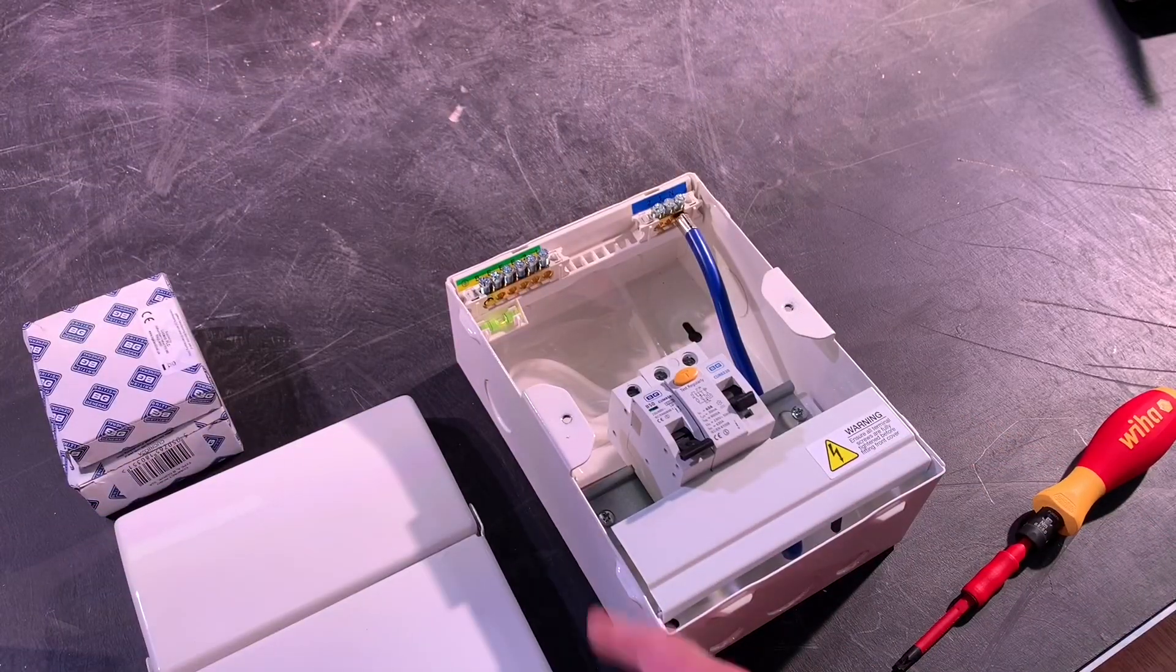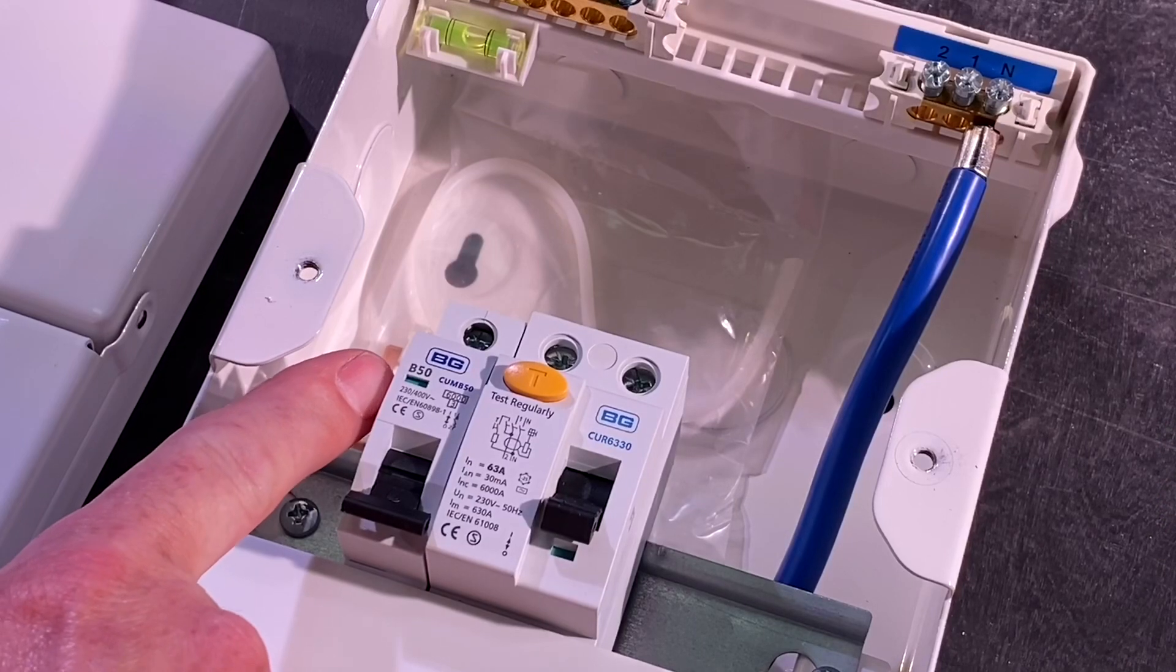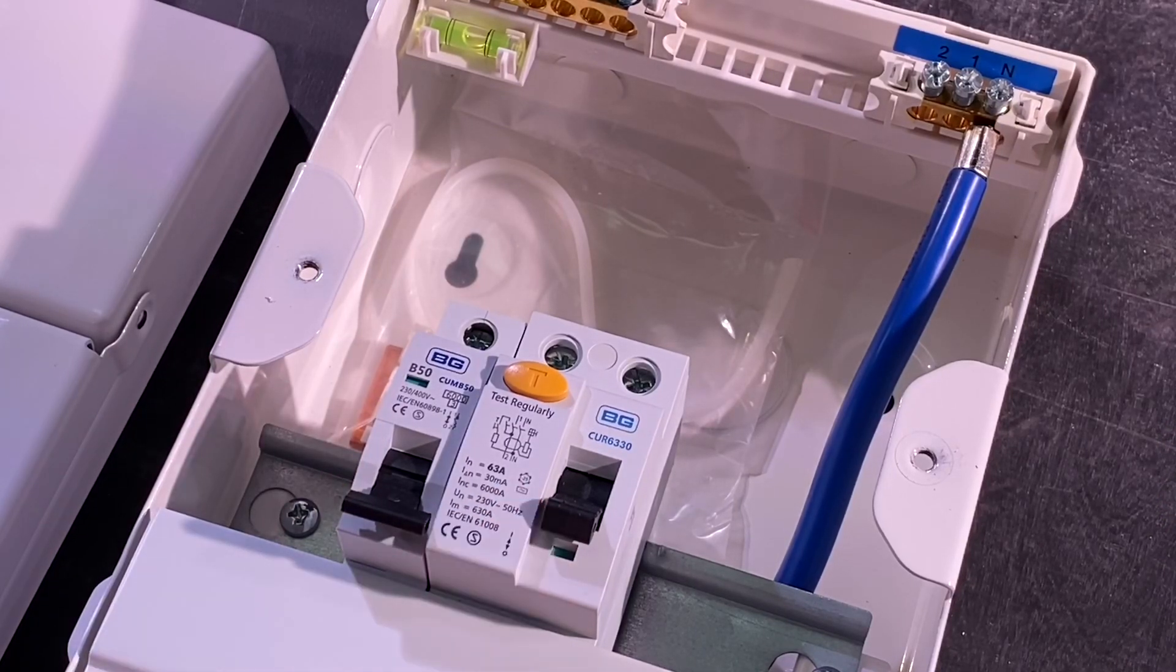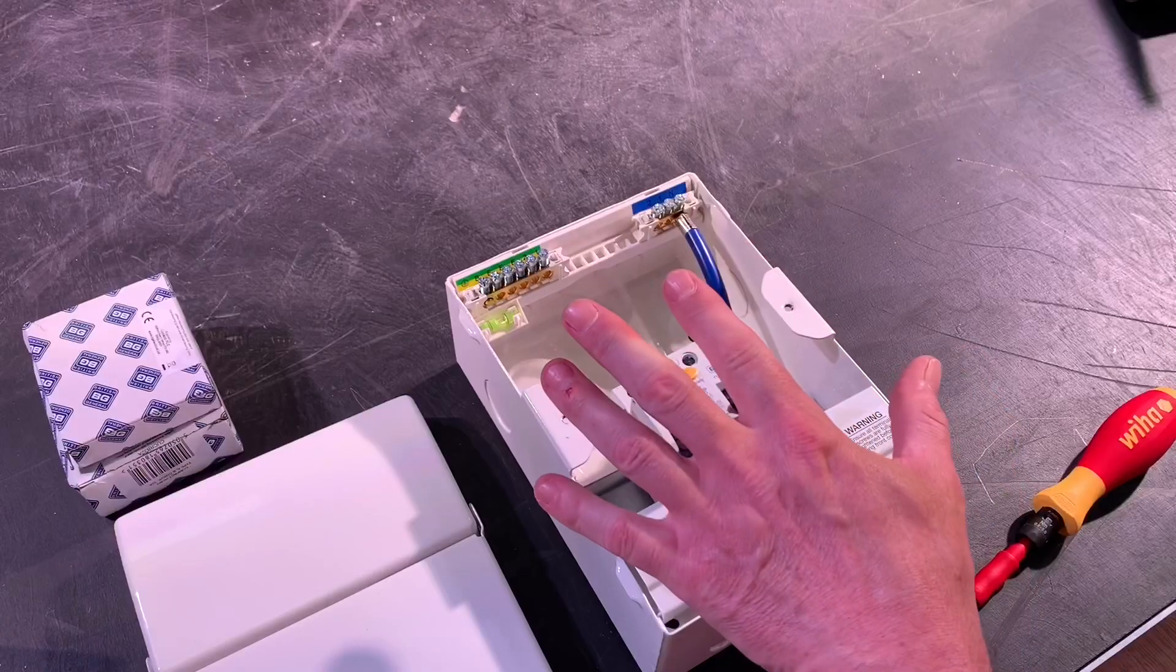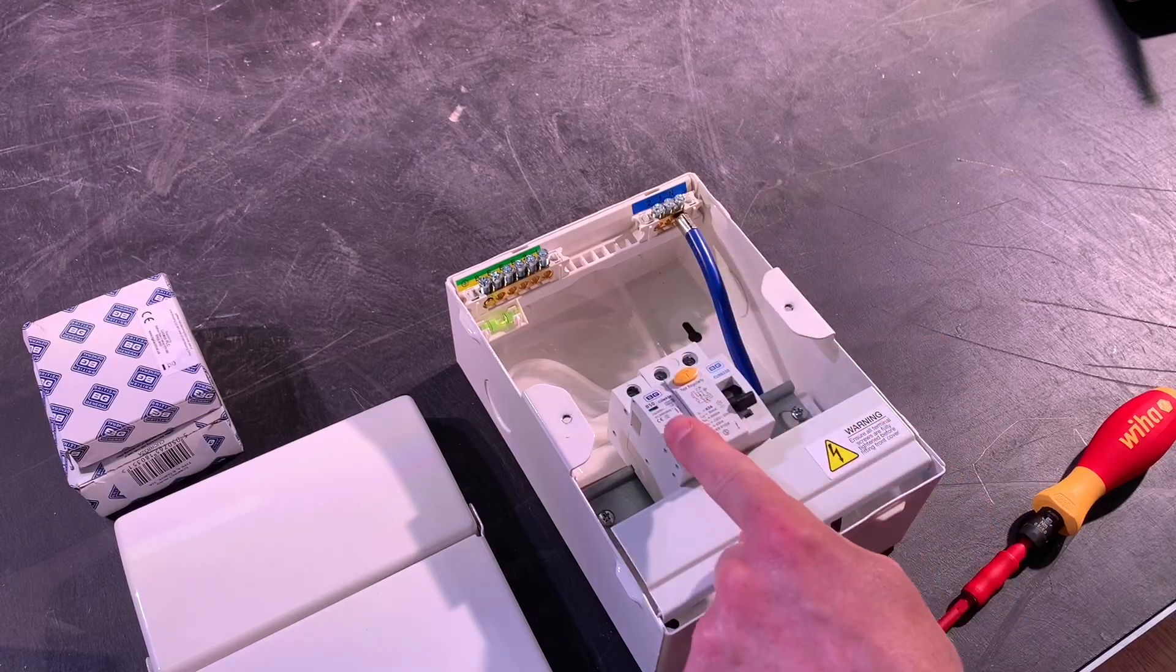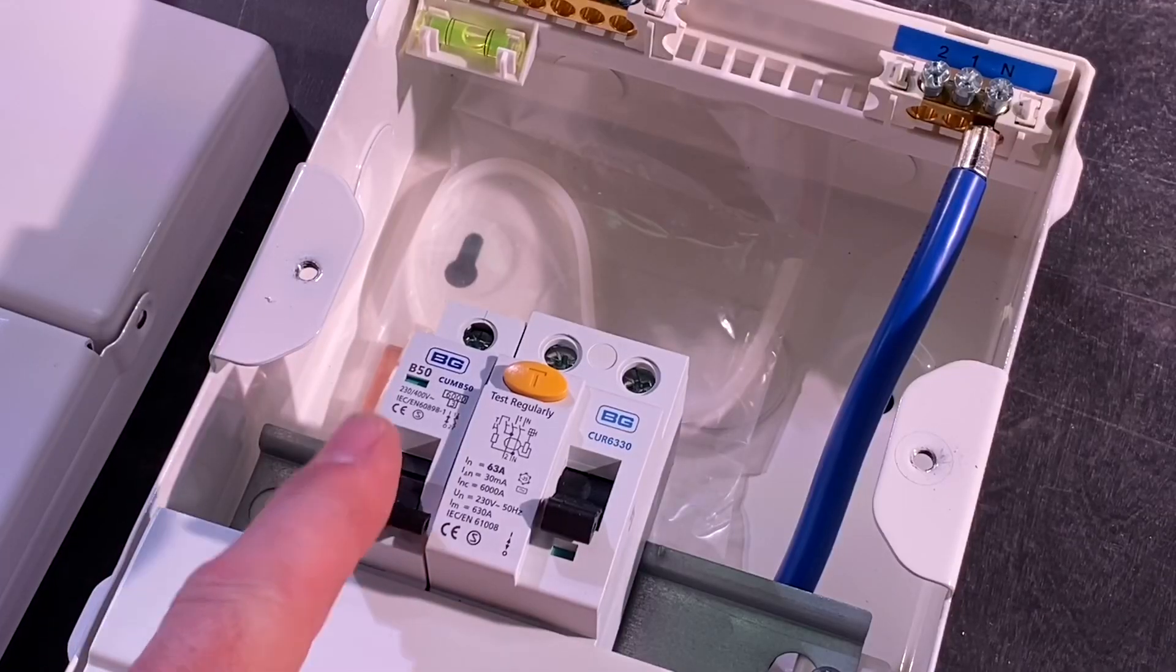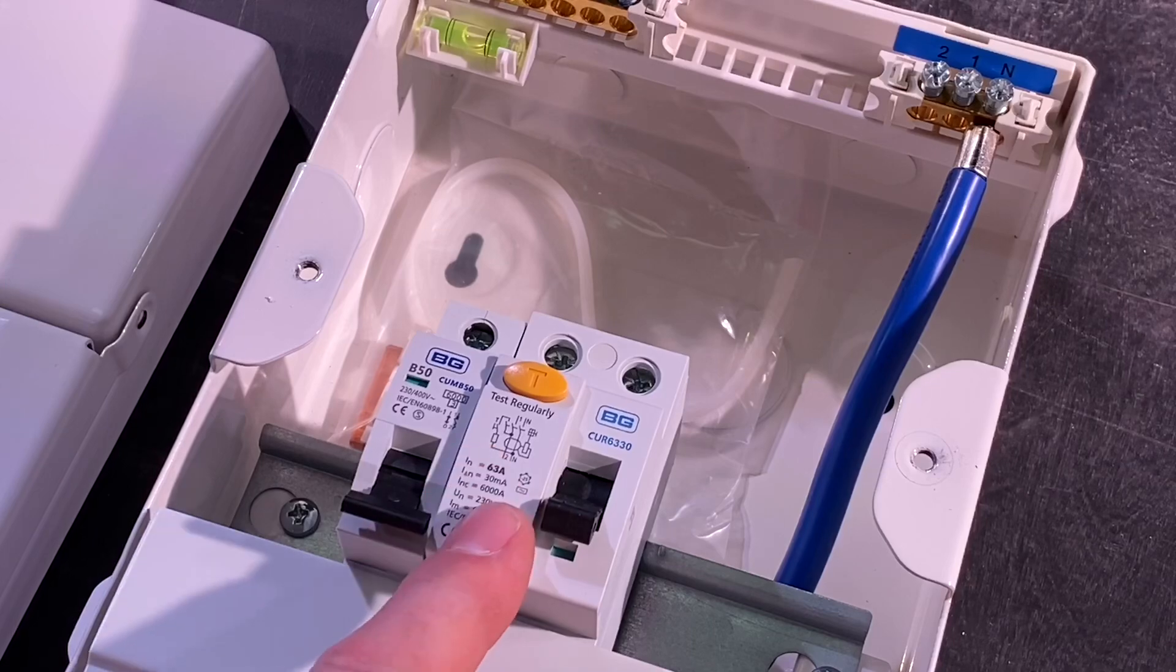We've got a B 50 amp circuit breaker provided with the consumer unit. The RCD is rated at 63 amps, 30 milliamps and is an AC type. Just stop you there, just remember that the shower itself is a resistive load and an AC RCD is totally acceptable.